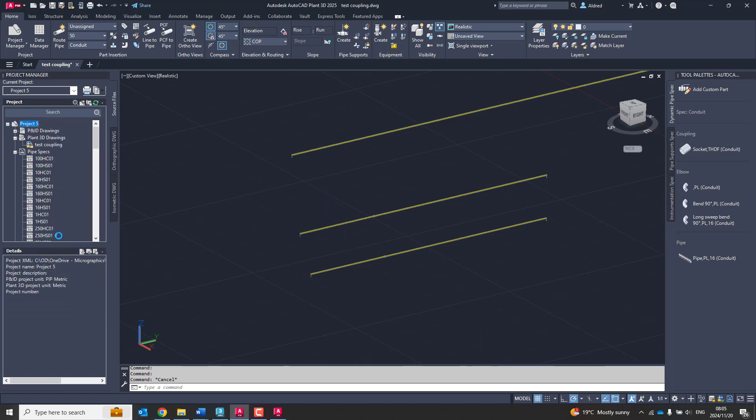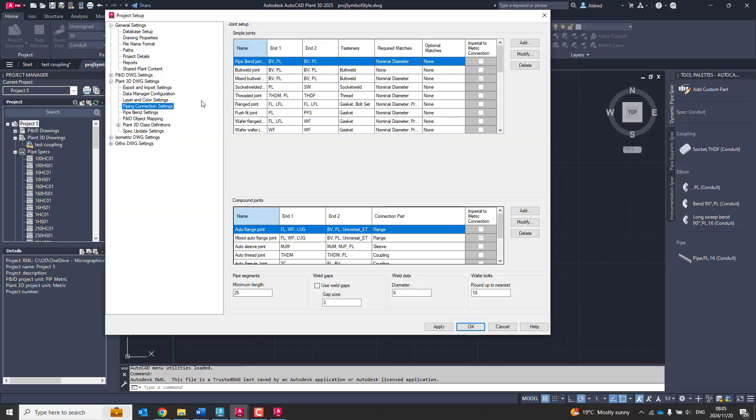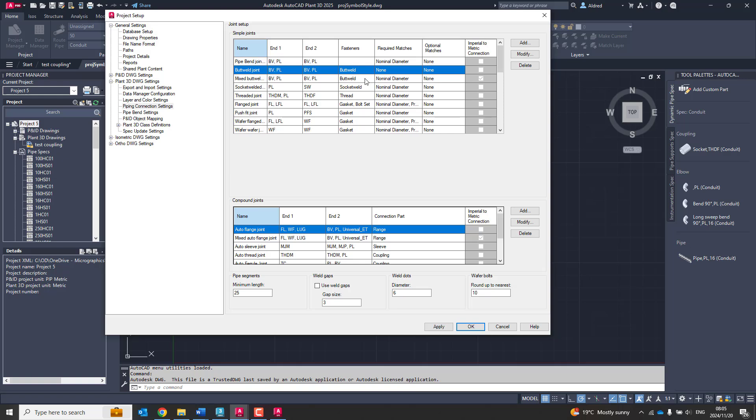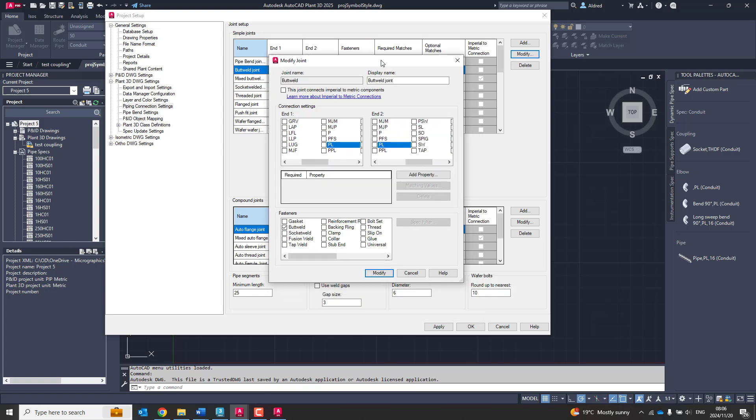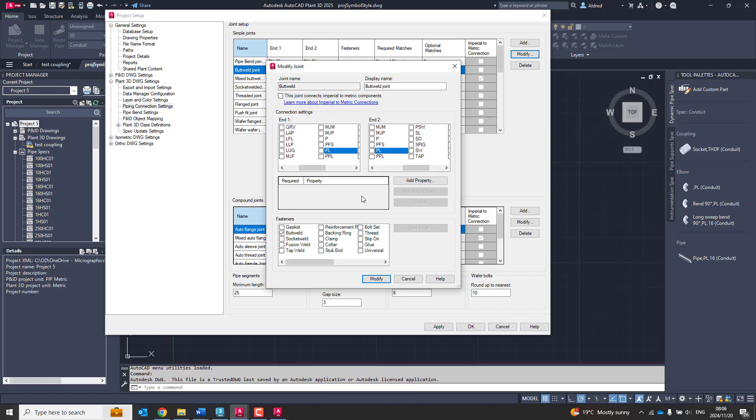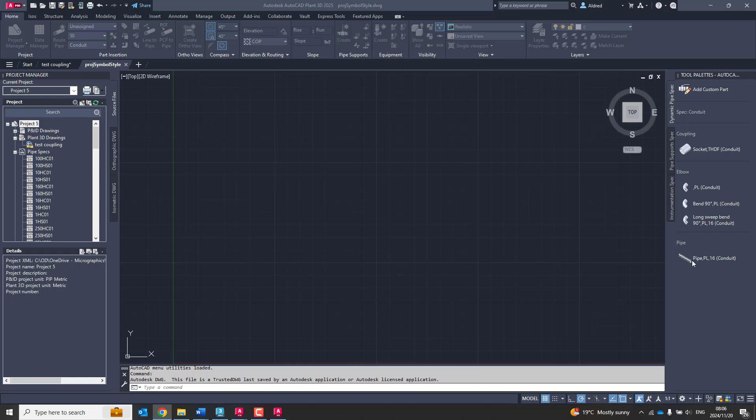So going back to my project setup, the simple joints is overriding the compound joints, and the one that it is doing is the back-butt weld joints over here. And because it's looking at BV PL, BV PL, or BV PL, or PL PL, or PL PL, or PL BV, it is first putting the simple joint before it's looking at the compound joint. So what I'm going to do is just modify this simple joint over here, and I'm going to remove the PL. Now, this is the simple way of doing it. What I should probably have done, because if I'm going to have other pipes that need this simple joint over here, I would then maybe create a new name for my connection, a new connection name in my AutoCAD plant. So let's go do that. Modify, click on OK, and let's see what happens now.